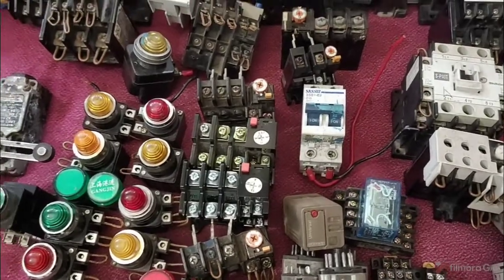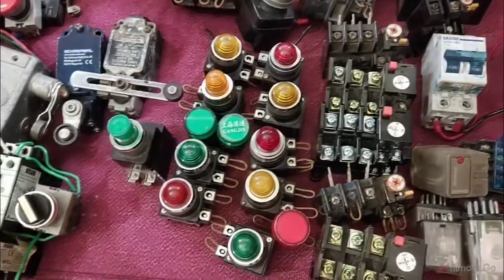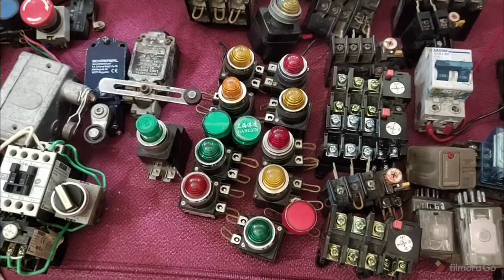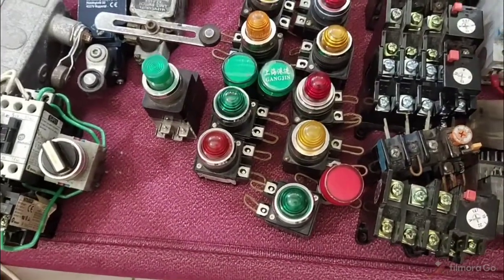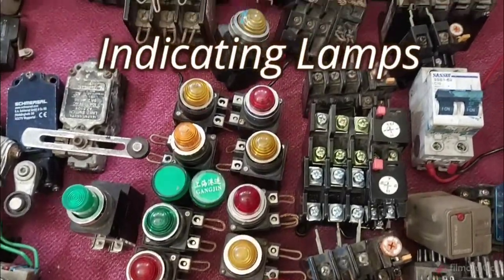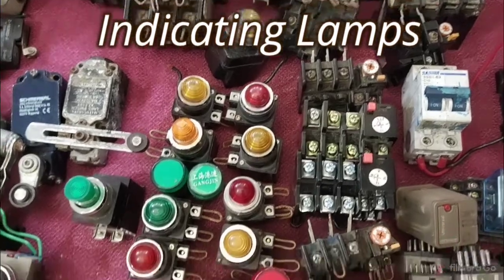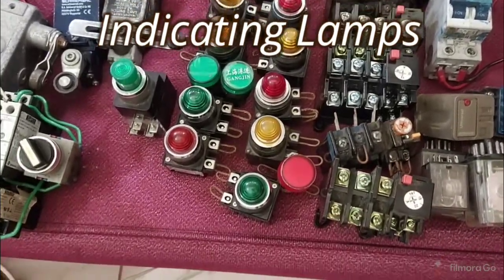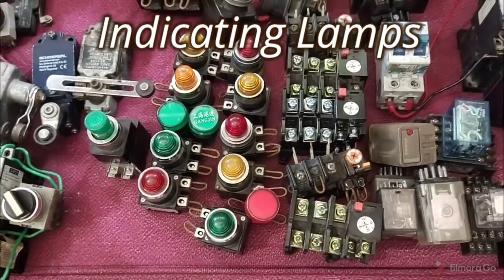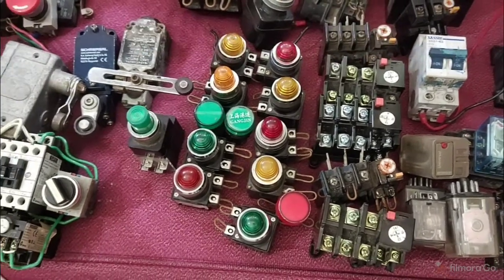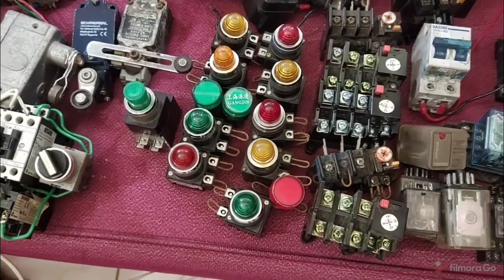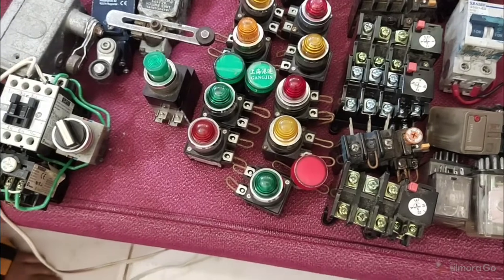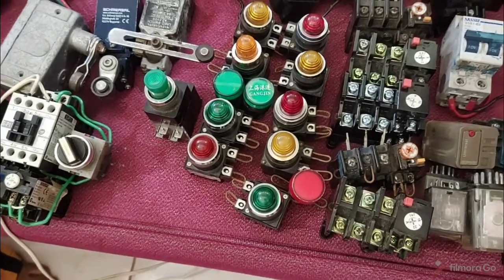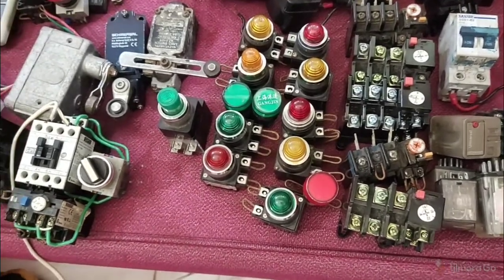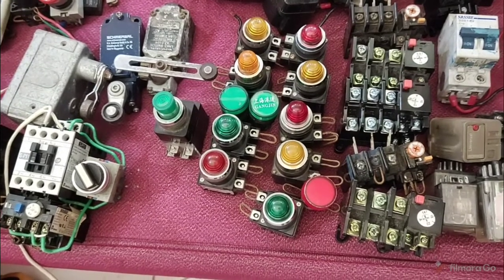And then we also have here the different indicating lamps. This indicating lamp is transformerized, meaning there's a transformer. It's rated 220, but the bulb is only 6.3, because this is what we call transformerized - so there's a primary winding and secondary winding. The voltage of the lamp is only 6.3 volts, but the input is 220.